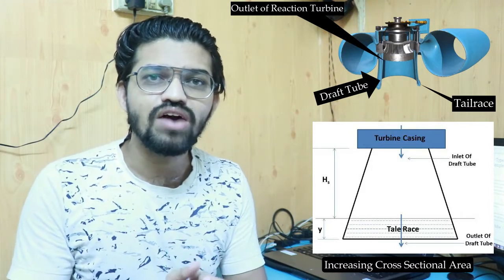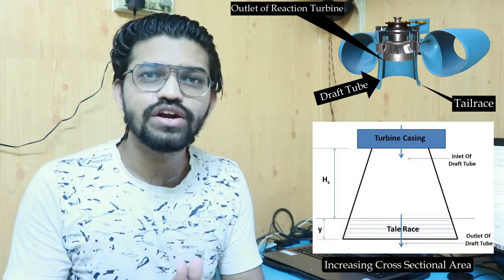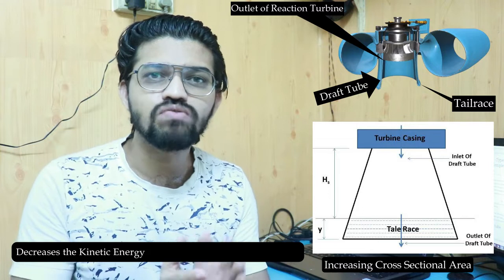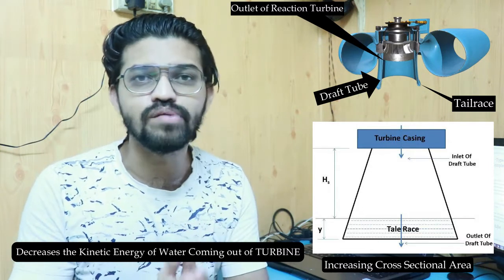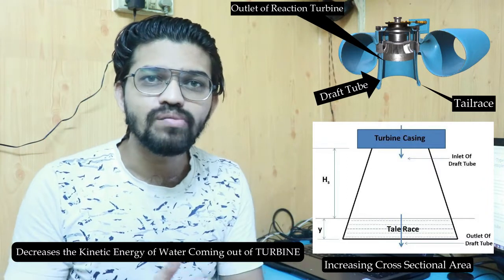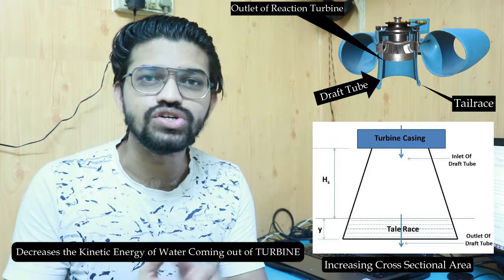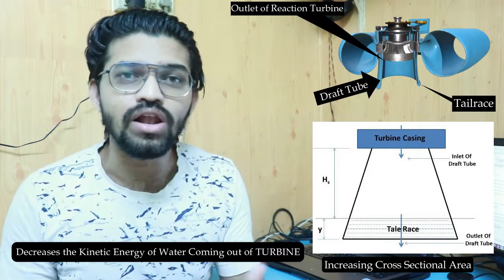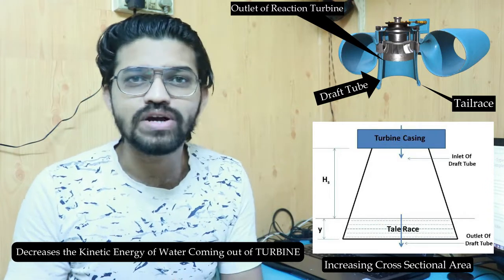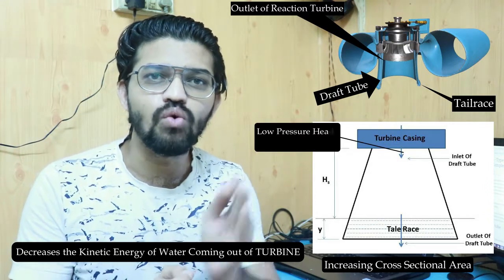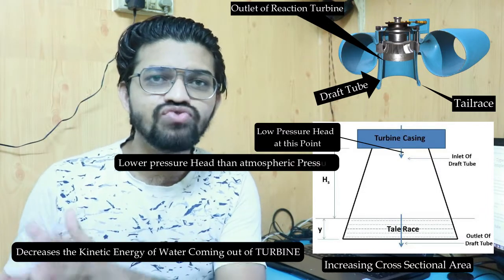This type of draft tube is suitable for the reaction turbine. The draft tube decreases the kinetic energy of the water coming out from the runner of the turbine. At the exit of the turbine, the water has higher velocity and higher kinetic energy, and it is in the form of a whirl. Also, this water will be having lower pressure — the pressure at the exit of the turbine is lower than atmospheric pressure.